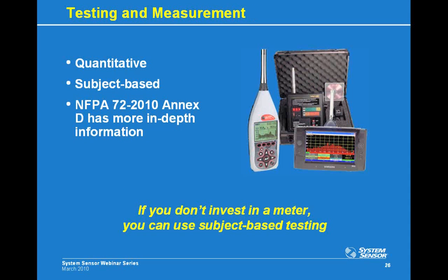When intelligibility is required and must be measured, more commonly quantitative methods are used for conducting intelligibility testing. This testing requires the use of an intelligibility meter, which is the most accurate and most feasible way of conducting intelligibility testing. These meters measure either the STI or the CIS test scores. Typically, they'll have the capability of measuring both depending on what setting is chosen.